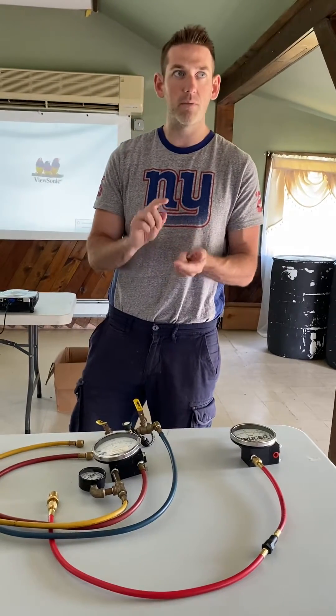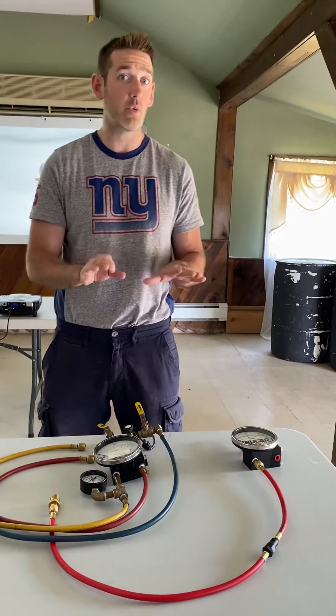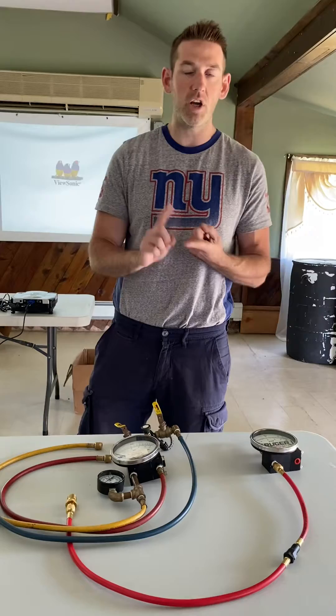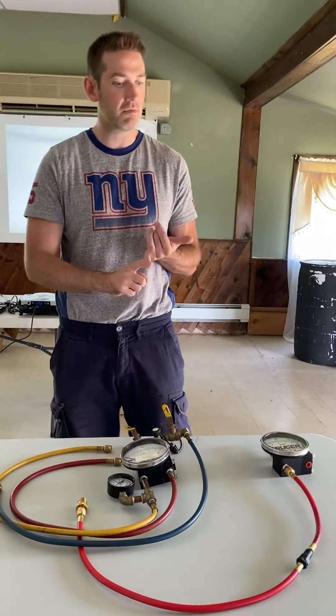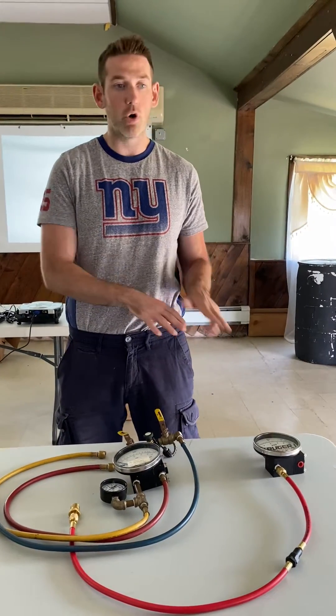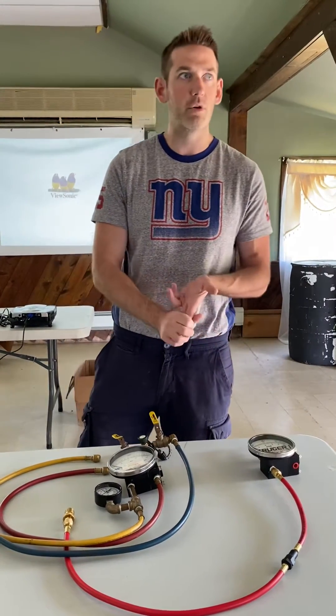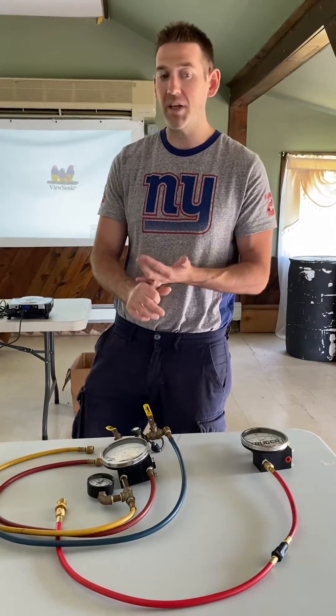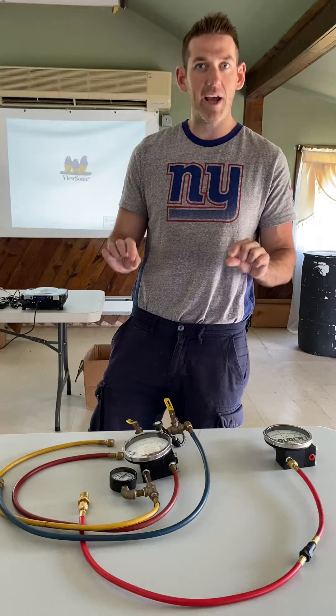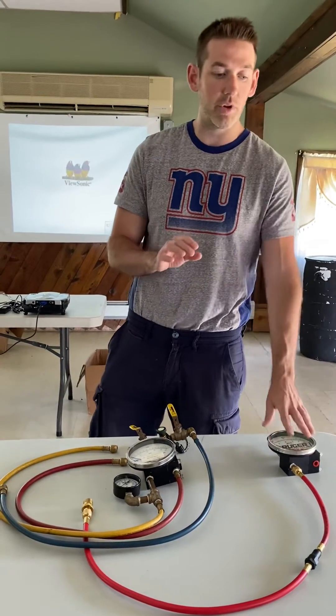The ASSE 5000-2015 test procedures — their new book — have included what they call the one-hose method for both the RP, double check, PVB, and the spill resistant. Most test procedures for the DCV and the PVB will only utilize one hose, but now they've added the RP. So now you can test any type of preventer, any place, per ASSE standards with only one hose.